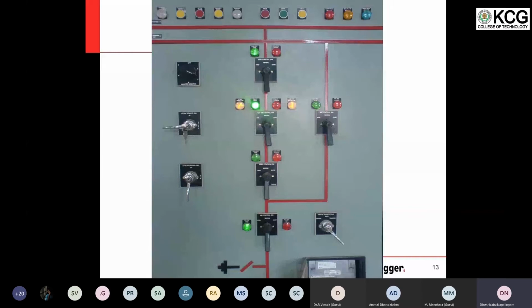Now imagine that someone sitting in the SCADA center, remote location, has directly given a close command to the breaker. What will happen to the breaker? It will close in 100 milliseconds, which is faster than the isolator closing time. Now what happened? The breaker will be closed before the isolator. Therefore, we are bypassing, or not following, or not complying with the logic that was discussed earlier.